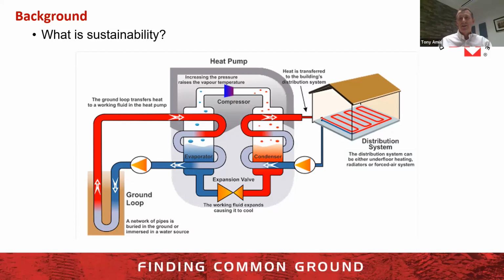So that added heat is then passed through an evaporator. And what happens there is there's a refrigerant in that evaporator that when we warm it up by that 5 or 10 degrees Fahrenheit, it moves it from a liquid state to a boiling state. And then we compress it. You can see the compression at the top there. And when you compress that boiling liquid, you convert it into a gas, which raises the temperature even further. So what we're looking to do is to take that low-grade temperature from the ground and convert it into 120, 130 degrees Fahrenheit in the building, sufficient to provide heating for hot water and heating systems within a building.